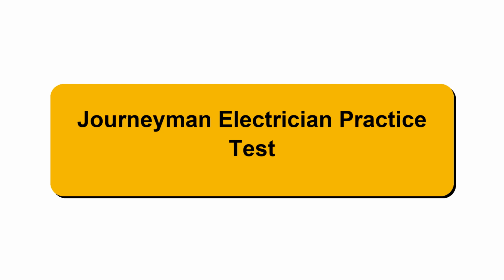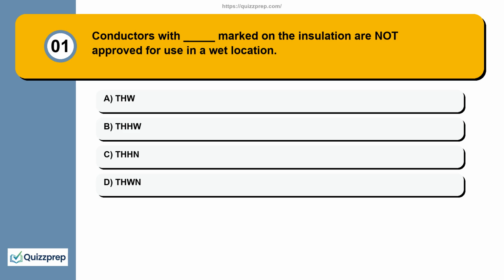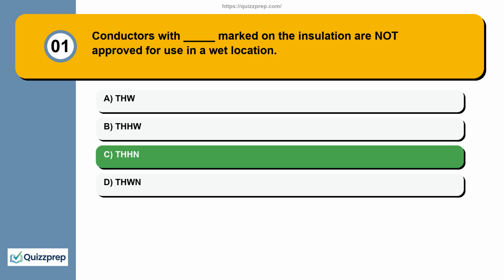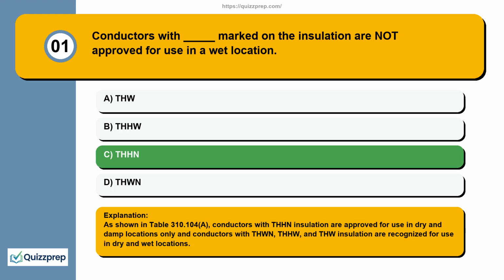Journeyman Electrician Practice Test. Question 1. Conductors with underscore marked on the insulation are not approved for use in a wet location. THW, THHW, THHN, THWN. As shown in Table 310.104a, conductors with THHN insulation are approved for use in dry and damp locations only, and conductors with THWN, THHW, and THW insulation are recognized for use in dry and wet locations.